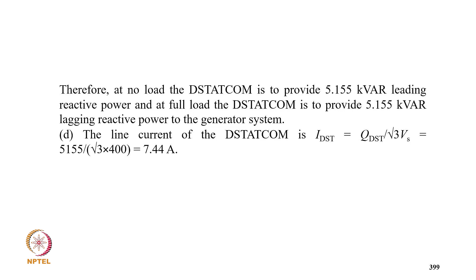Now coming to example 10. A STATCOM with a 660 volt battery at the DC side of the VSC is connected to an isolated 3-phase 3-wire 415 volt 75 kVA diesel generating set system as shown in the figure. This DG set is controlled such that the load on the system remains always between 80% to 100% to improve the efficiency of the DG system. There is a load shedding provision if the load increases above 125%. If the load is below 80%, the battery charging takes place.